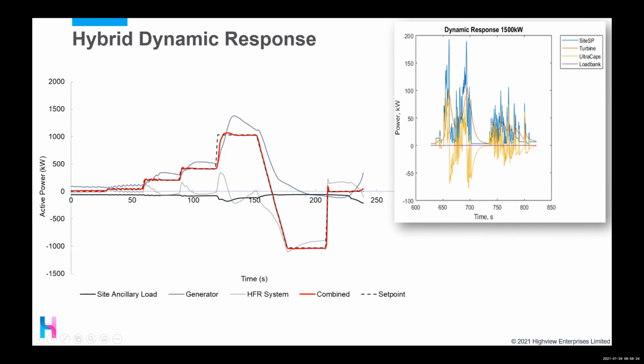On the right hand side, you can see we were able to do much more complex responses. This is a site set point for load following and for frequency response, quite a complex waveform, and we're following it. The orange line, if you can just make it out, is our turbine response, the yellow is the ultracaps, and the purple, which isn't required for this particular one, is our load bank. The net effect, the blue, follows the blue shape.